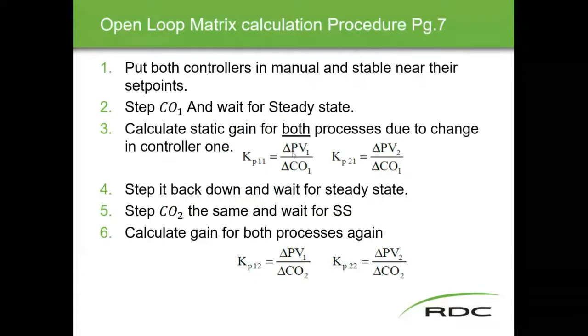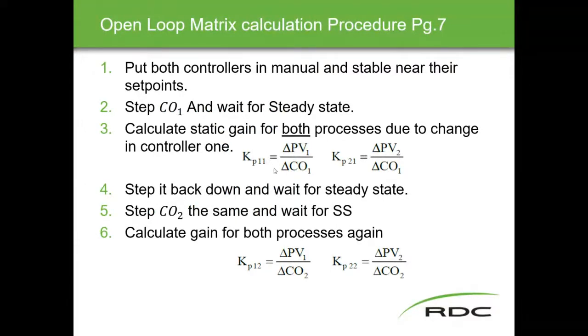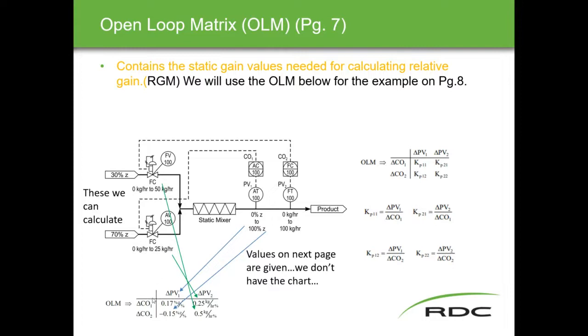To get the static gain values, we make a change in controller one, measure how much it affected PV1 and how much it affected PV2, then put them over each other. That gives us KP11, KP12, KP21, and KP22 values. You do it first with one controller and then with the other. The math is essentially output over input.